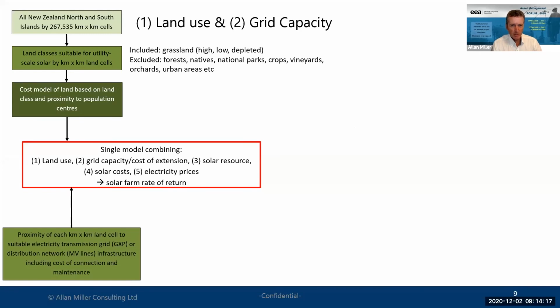The second input is proximity to grid exit points and medium voltage lines. The model actually builds a notional transmission line to the nearest grid exit point with suitable capacity, and incorporates that as a cost into the solar farm. For distribution connected, it only considers land within about 1 kilometre of a medium voltage line, on the assumption that no small scale solar farm can really afford to build a large line connected to medium voltage. However, between 5 megawatts and 20 megawatts, we did consider them building a 33 kV line to the nearest zone substation, with the existing 11 kV line underbuilt.